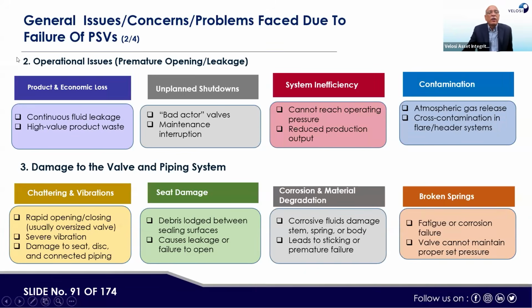Then operational issues. For example, if the PSV is not working properly, there could be product and economical loss. If the PSV is leaking, fluid would be lost. It could also lead to a high value of product waste, and unplanned shutdown. First of all, what are the failure modes, if I may bring them in? The PSV generally has 3-4 problems.